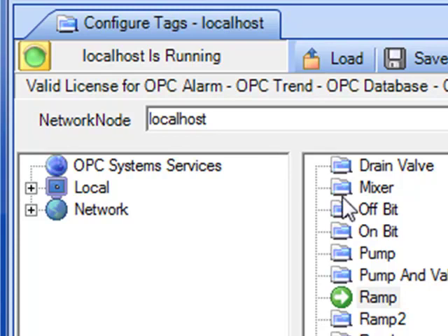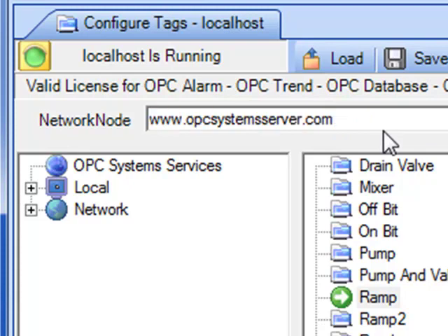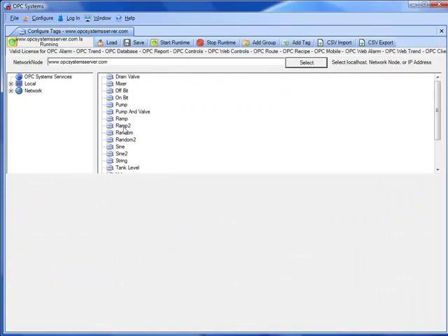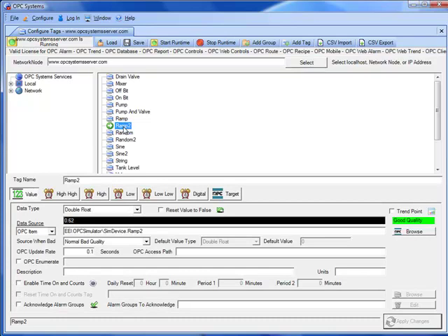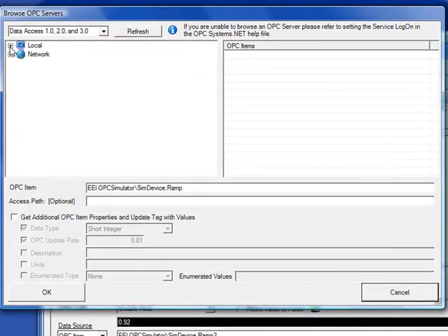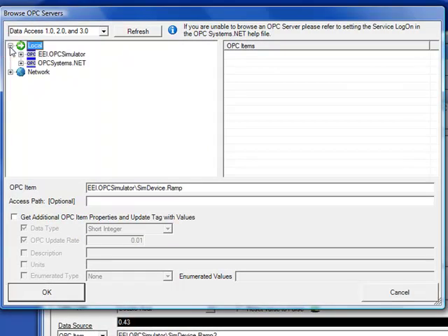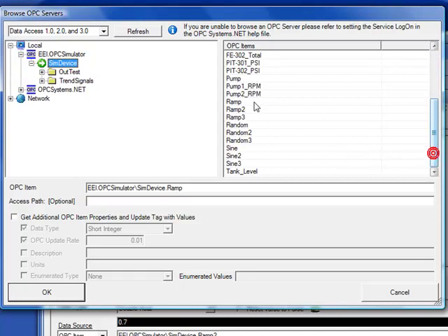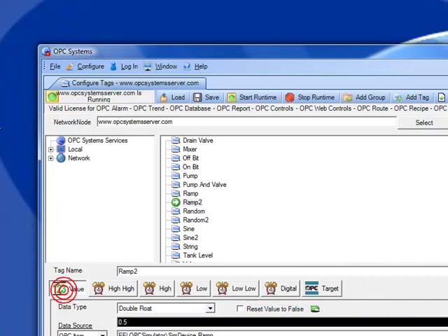Let's see how to configure a remote real-time database. In the network node field at the top, you can put in an IP address, network node name, or a registered domain name — in this case opcsystemserver.com. When we hit the Select button, we are now connected to a system registered in Texas, and as long as you have an internet connection, you'll be able to see those tags and their properties. If we used OPC server browsing, we would still use the local connection for browsing, because we want that server to browse OPC servers local to it, even though we are configuring a system across the internet. You can see that the item path returned is a local OPC item, but the service is running remotely.